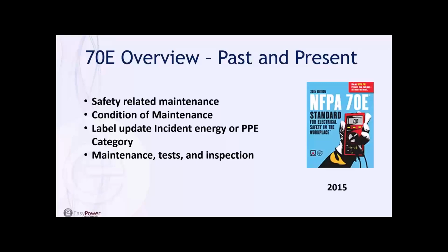The very mission statement of 70E in 2015 was changed to include the language 'safety-related maintenance.' Condition of maintenance was also one of the key categories, and maintenance, test, and inspections continued. There were also updates to the incident energy or PPE category methods for what goes on an arc flash label — those became 'one or the other,' exclusively, as written within the standard.